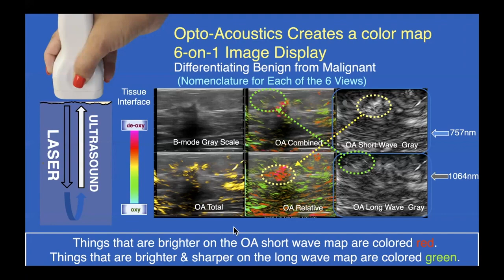And so the next thing that's created is a total hemoglobin map. Here we don't distinguish oxygenated from deoxygenated. It's colored yellow, and it's a combination of oxygenated and deoxygenated. That gives us a total hemoglobin map. Then that's used as a map on top of the OA relative to create the OA combined. And generally, OA total and OA combined, we use about 90% of the time to make the interpretation, but there are instances in which the OA relative is better.